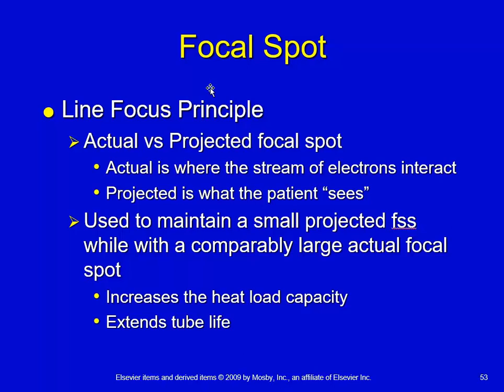The line of focus principle allows us to use a steep angulation on the anode to project a smaller focal spot off of a larger focal spot. This gives us a larger area to deposit electrons so the anode doesn't take them all in a single spot — it spreads the heat out, extending tube life. We're using a relatively large actual focal spot but, with the angulation, we get a very small projected focal spot, increasing sharpness and recorded detail while increasing heat load capacity.